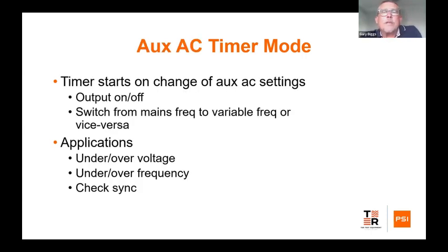We then have the auxiliary AC timer mode. So that uses the auxiliary AC channel. If I was not testing using the main channel, but using the auxiliary AC channel, it then links to that rather than the main channel and allows me to do other types of relays. Or if I'm doing dual output, I can then time it not from the main channel, but from that auxiliary channel. It's up to me. I've got full control over the set.